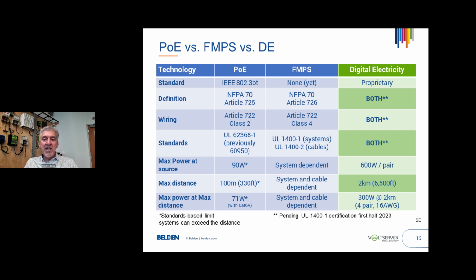So in that meantime, we'll still be teetering back and forth between Article 725 and 726 installations. The wiring standards, you can see, are both under Article 722 in the National Electric Code, and the safety standards, as I talked about before, PoE and digital electricity current implementations are UL 62368-1 listed systems, and then fault-managed power will be under the new UL standards, which are UL 1400-1 for the equipment, and UL 1400-2 for cables.